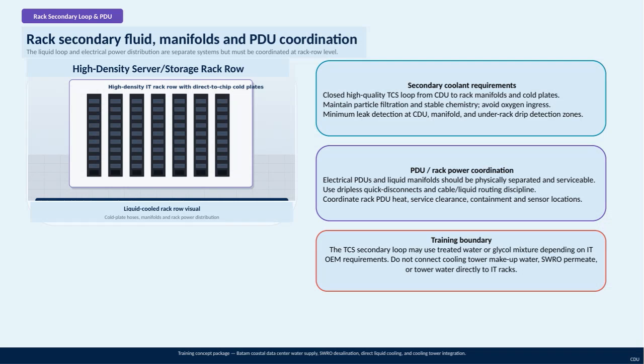On this slide, we're focusing on the coordination between the rack's secondary fluid loop and the power distribution units, or PDUs, within a data center environment. Even though the liquid cooling loop and the electrical power systems are fundamentally separate, it's critical to manage them together at the rack row level to ensure reliability and efficiency.